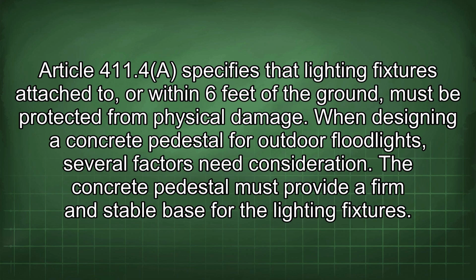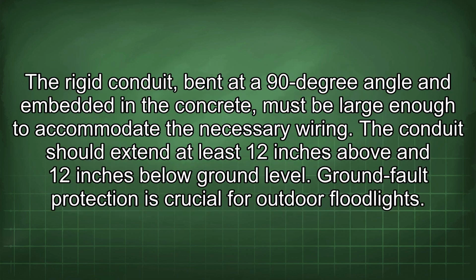When designing a concrete pedestal for outdoor floodlights, several factors need consideration. The concrete pedestal must provide a firm and stable base for the lighting fixtures. The rigid conduit, bent at a 90-degree angle and embedded in the concrete, must be large enough to accommodate the necessary wiring. The conduit should extend at least 12 inches above and 12 inches below ground level.